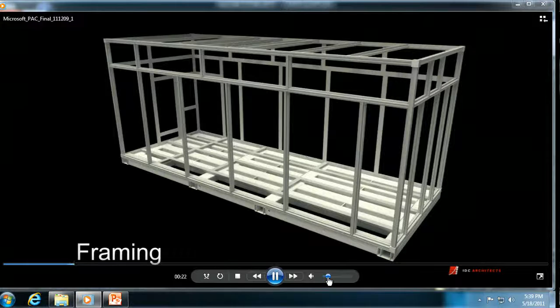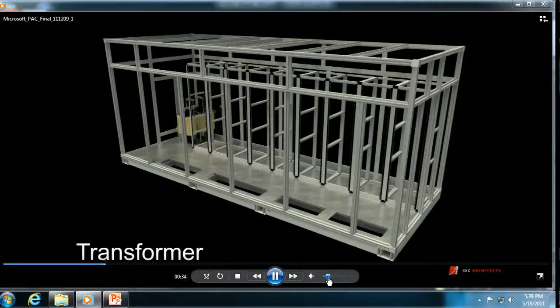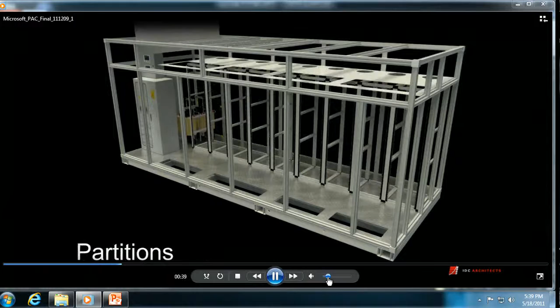What I need to operate this is about 640 kilowatts of power, two fiber channels, and a garden hose. The reason I need a garden hose is we're only going to run water flow above 95 degrees Fahrenheit in this demo. Our actual adiabatic engagement point is 85 degrees — we've changed that since this design — but ultimately you only need the water at the high end.